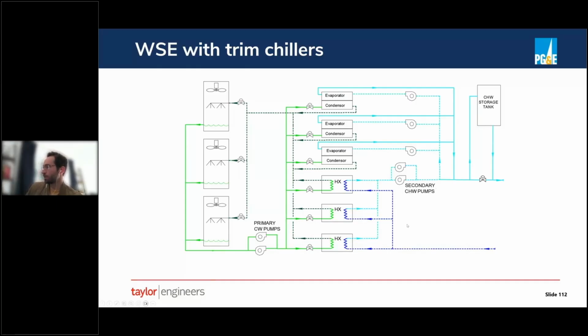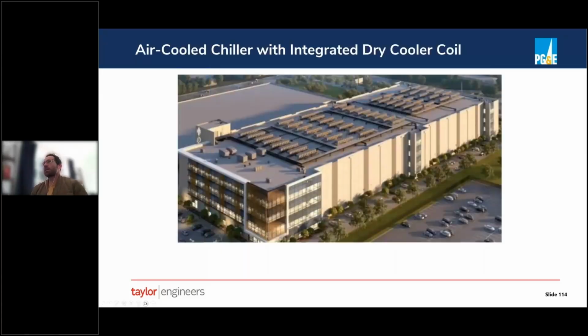So the basic idea is that the chilled water return comes back from the load. It first flows through the waterside economizer heat exchangers to do as much cooling as possible. And then only the remaining trim load is handled by the water-cooled chillers, which again are in series with those heat exchangers. All right, some other options.